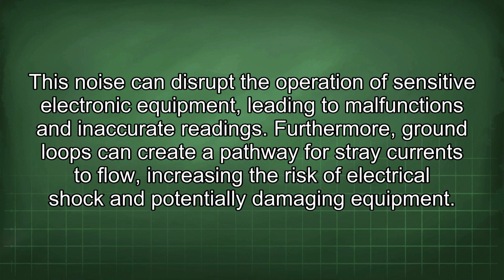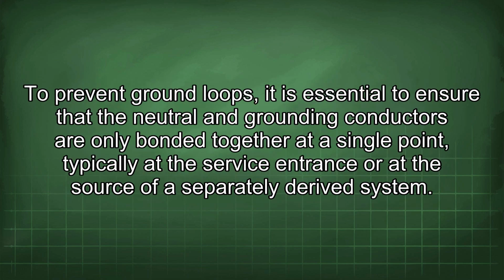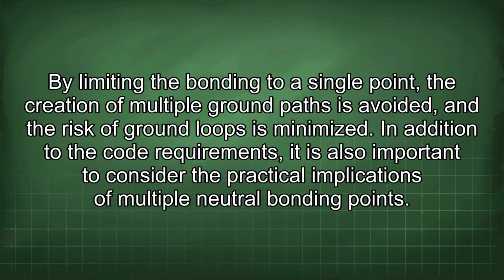Furthermore, ground loops can create a pathway for stray currents to flow, increasing the risk of electrical shock and potentially damaging equipment. To prevent ground loops, it is essential to ensure that the neutral and grounding conductors are only bonded together at a single point, typically at the service entrance or at the source of a separately derived system. By limiting the bonding to a single point, the creation of multiple ground paths is avoided, and the risk of ground loops is minimized.